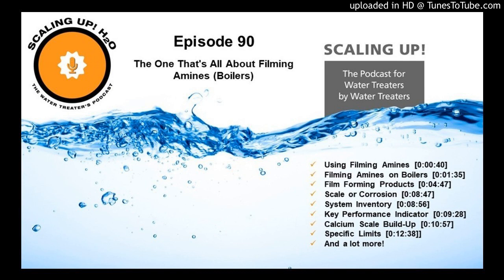So my initial mantra for everyone who is new to filming amines, or I should say has a known fouled system, is slow and low. Your vendor's going to give you a target dose. I'm going to make up numbers for easy math. Let's say that target dose is 1,000 parts per million. And at 1,000 parts per million, we feel comfortable saying that in 90% of the situations, 90% of boilers at 1,000 parts per million of product, we can effectively treat an entire system.